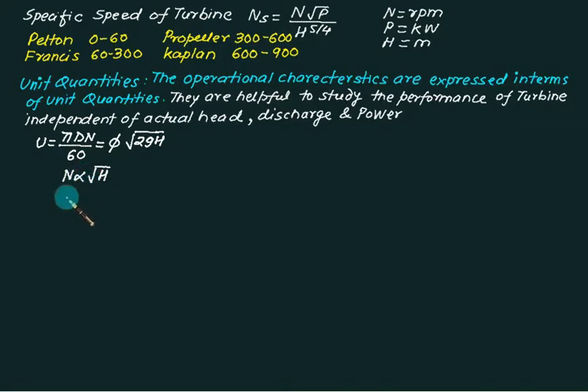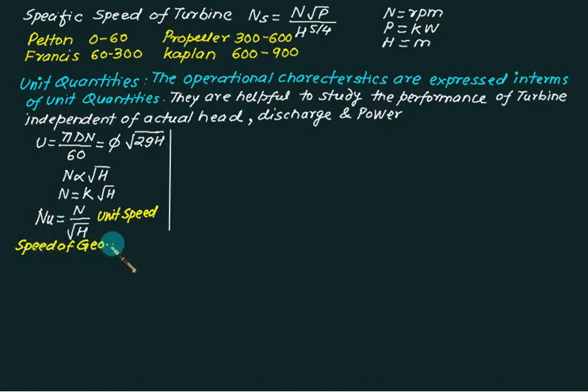So we have n equals to certain constant times root h. We have a unit speed nu equals to n by root h. So constant k is called as unit speed, with the speed of geometrically similar model turbine working under a head of 1 meter.